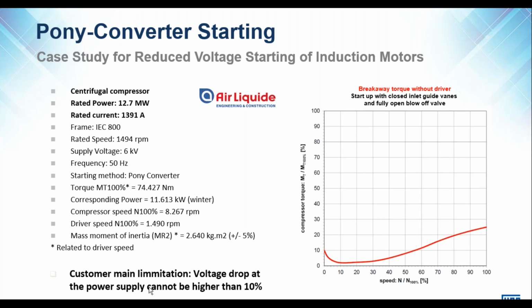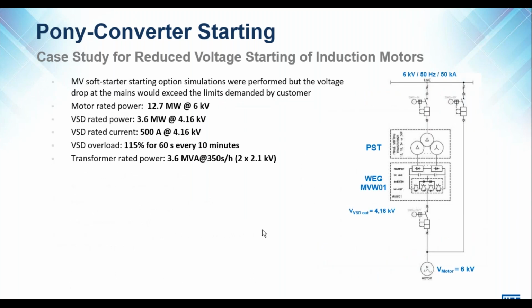One other consideration here was the voltage drop requirements. In fact, one of the main reasons that they used a VSD to start this compressor was because they could not handle a high voltage drop, and the power supply was fairly low capacity. So we made use of a 12.7 megawatt motor, but the VSD rated power was able to be reduced to 3.6 megawatts and at a reduced voltage of 4.16 kV.